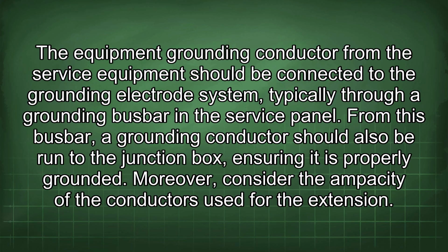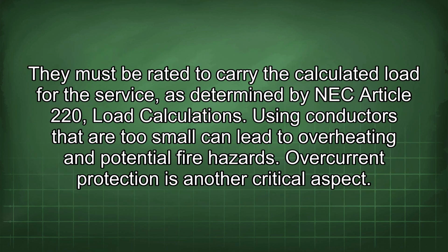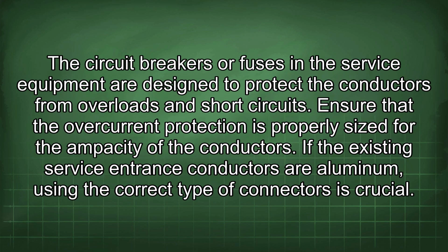Moreover, consider the ampacity of the conductors used for the extension. They must be rated to carry the calculated load for the service, as determined by NEC Article 220, Load Calculations. Using conductors that are too small can lead to overheating and potential fire hazards. Overcurrent protection is another critical aspect. The circuit breakers or fuses in the service equipment are designed to protect the conductors from overloads and short circuits. Ensure that the overcurrent protection is properly sized for the ampacity of the conductors.